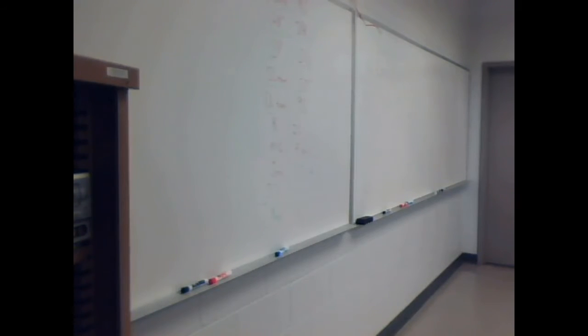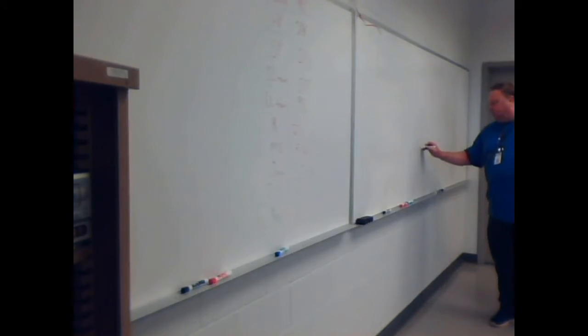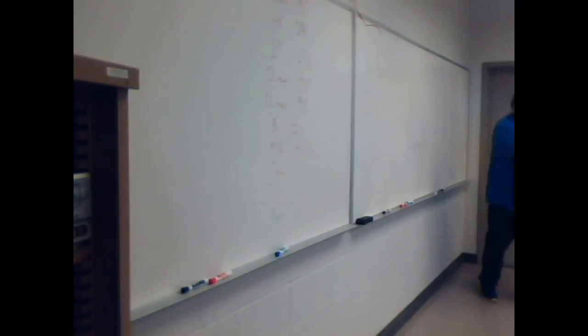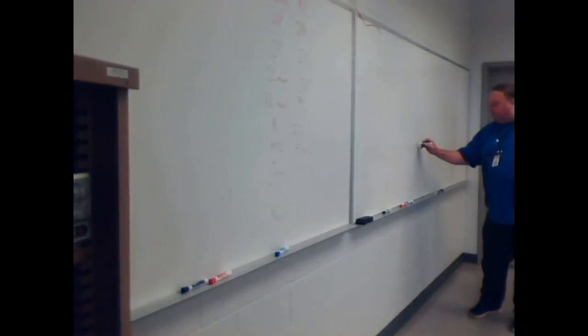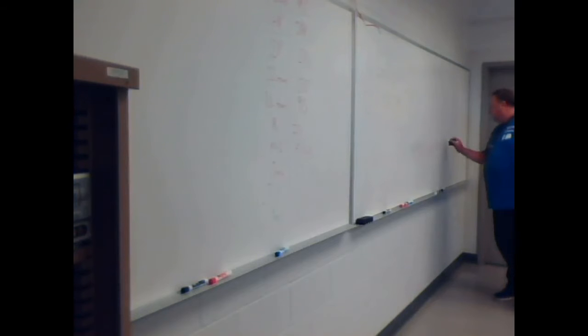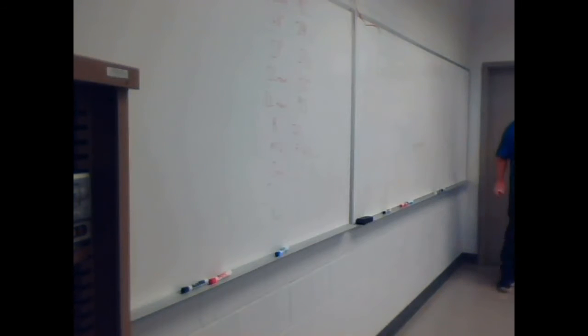That's just the definition of superheat, right? When I change any substance to a vapor, if you add any more heat to it, we're going to call it what? Superheat. Doesn't have to be refrigerant, it could be water, it could be anything. And at 100% liquid, if I remove any heat from it, that's called subcooling.